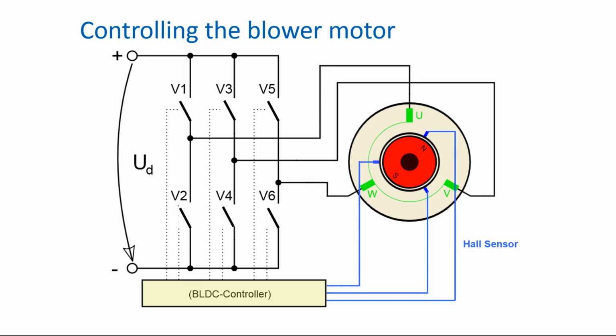The switches open and close in a frequency so that only one coil pair gets current at a time. In this example, current flows through V1 to U and V on the motor side, and then through V4 to ground.